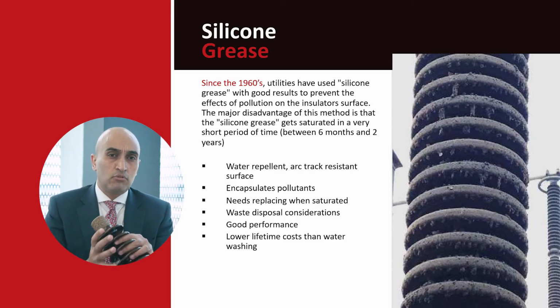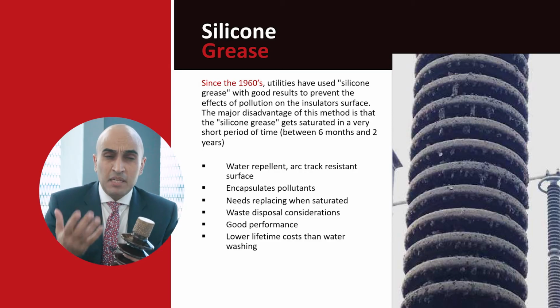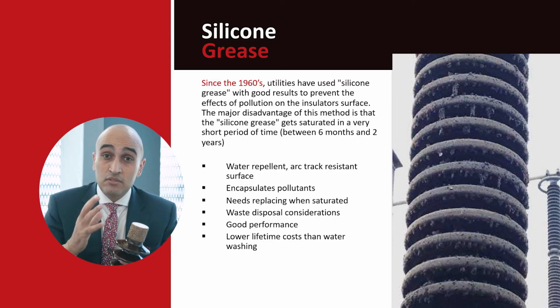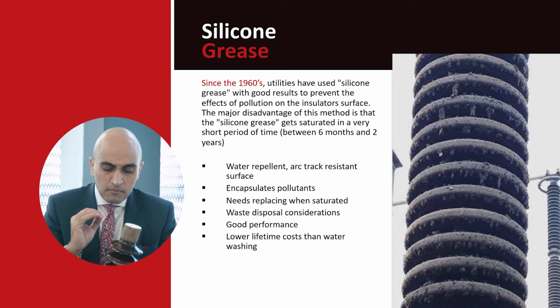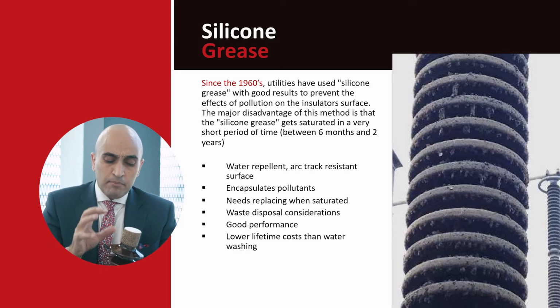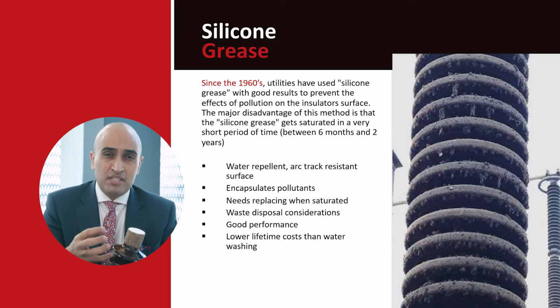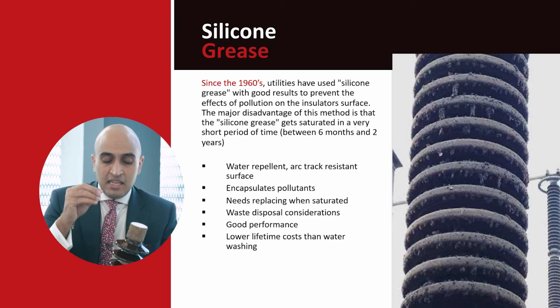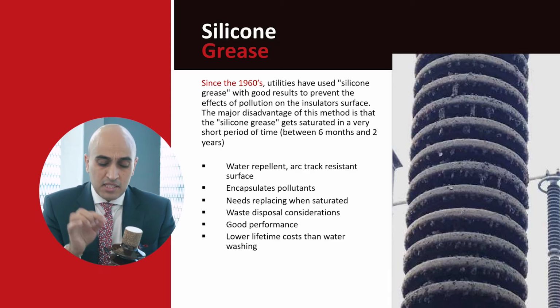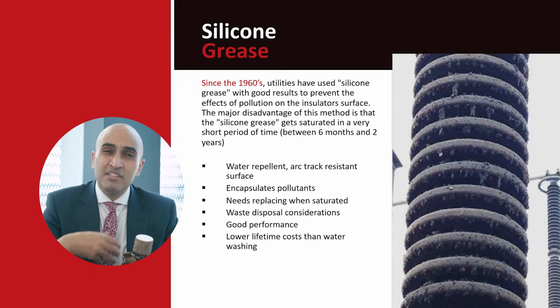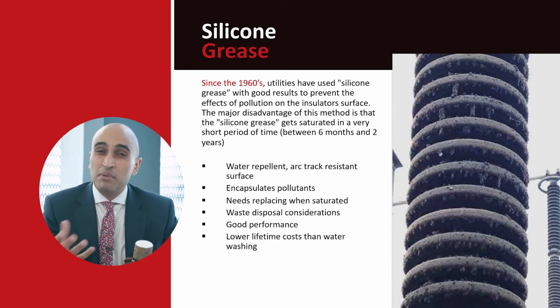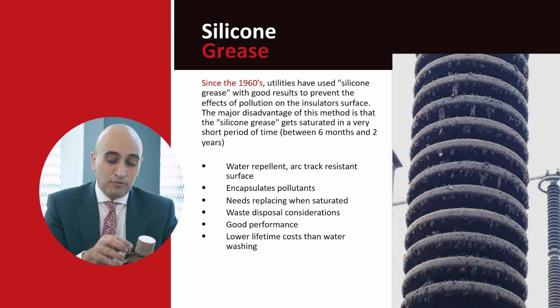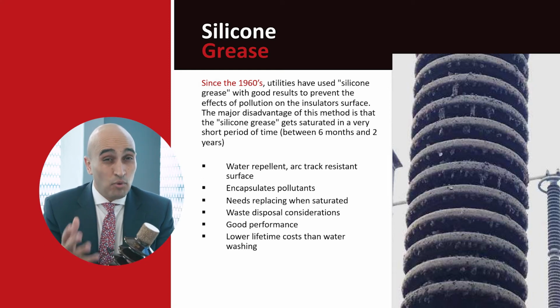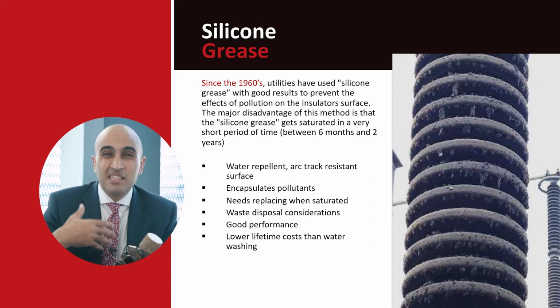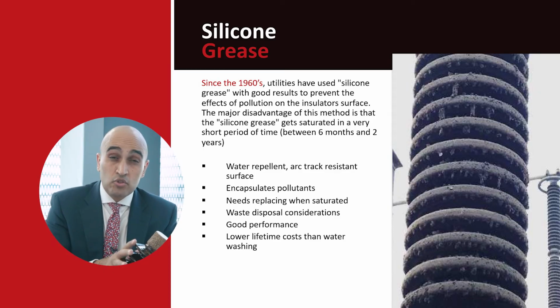Let's talk first about silicone grease. Silicone grease was implemented back in the 60s, and it has been a very good solution, giving very good results. The main problem with the silicone grease is it saturates very fast. It means that in very contaminated environments, the silicone grease will be saturated and we will need to remove it every 6 months, maximum a year or two. And the removal of the silicone grease is very, very tough work, and also has increased costs. So the silicone grease works to mitigate the problem, however, it's also a temporary solution.